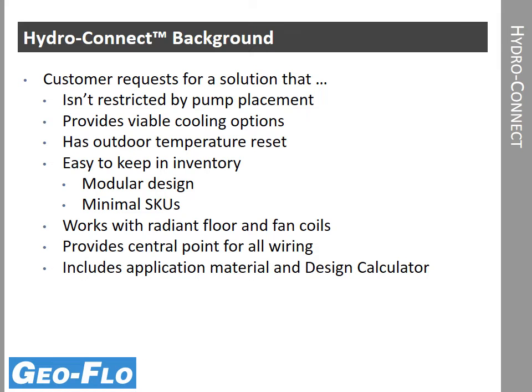A little bit of background on the Hydroconnect system. It was built from many customer requests for a solution that doesn't restrict pump placement. In some systems, the pumps must be placed on the tank itself, but it's not always the most convenient location. And so the Hydroconnect system gives you the flexibility to put the pumps where they look best and function the best in the mechanical room. It also provides viable cooling options.